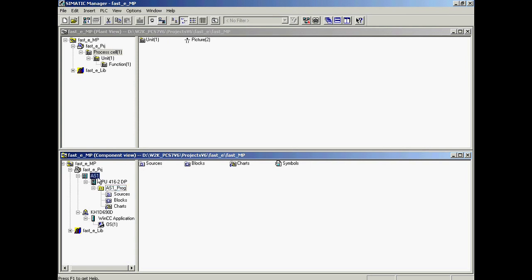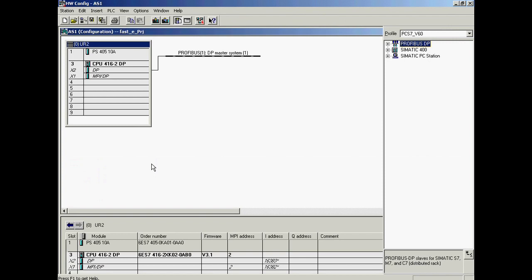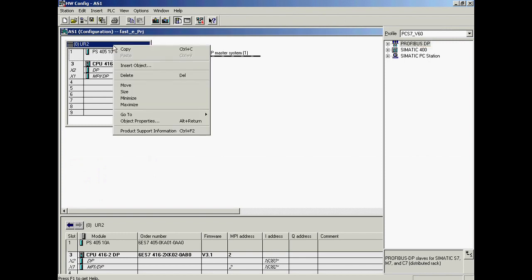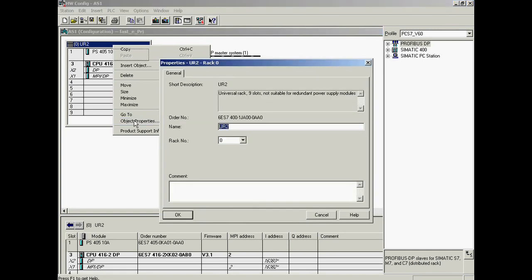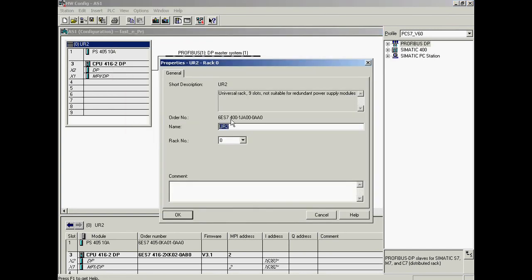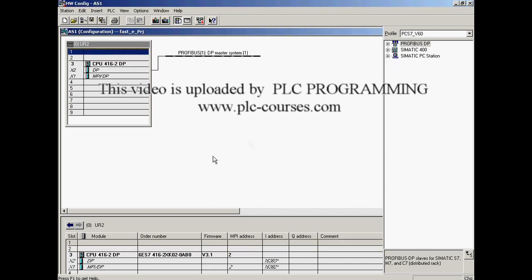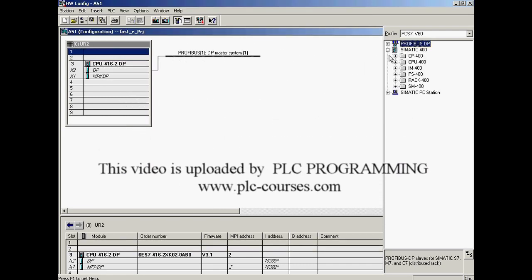Now the automation system is configured. In the first step, we check whether the preset hardware components in the wizard match the actual components. First, the rack is checked — the part number matches the actual hardware. Now the power supply is checked — the part numbers don't match.